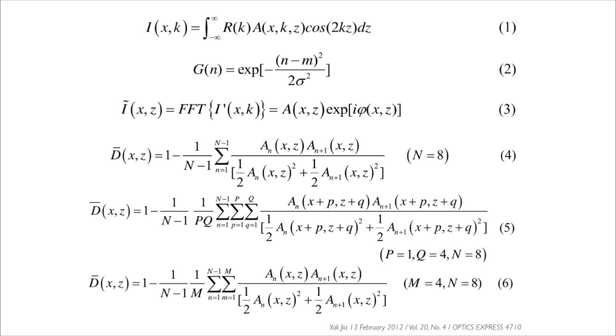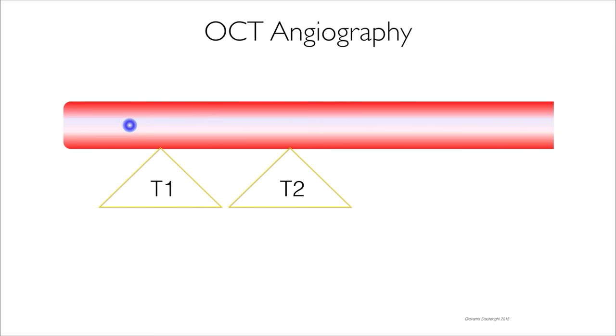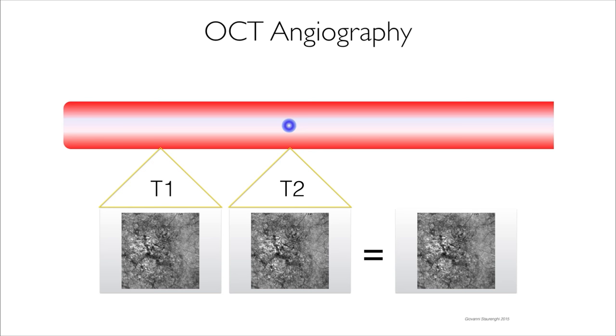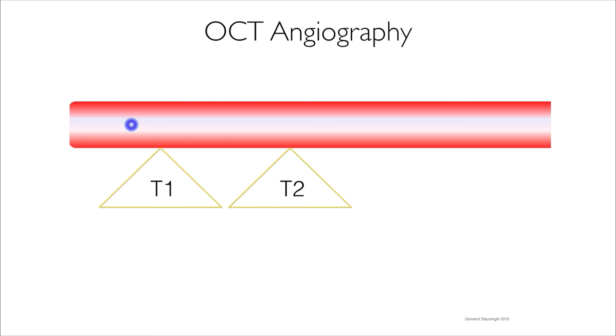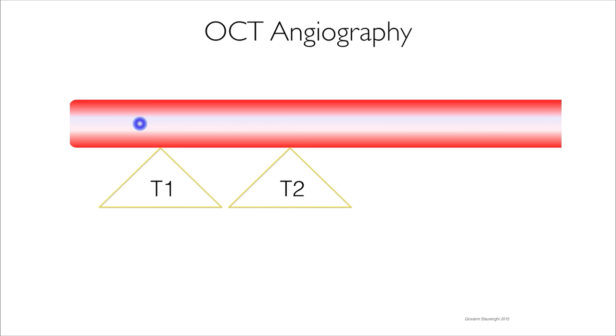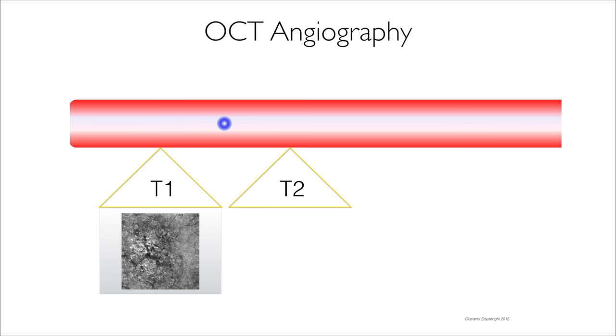What I understand from angio-OCT is that you have at least two time points - at least the commercially available instruments have only two time points. If you see something moving in the vessel at time one and time two, you get an image. If something is moving too fast, there is no image at either time point. But remember it can also be the opposite: too slow flow means you get an image at time one but not time two, and so you don't get an image.